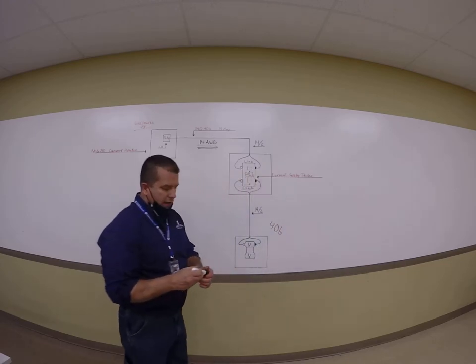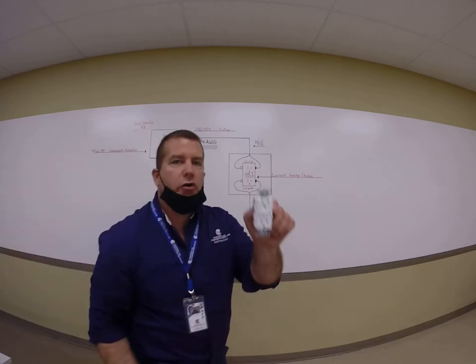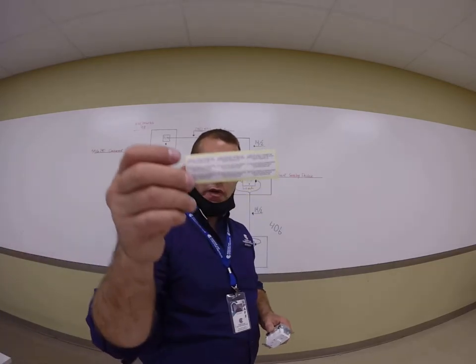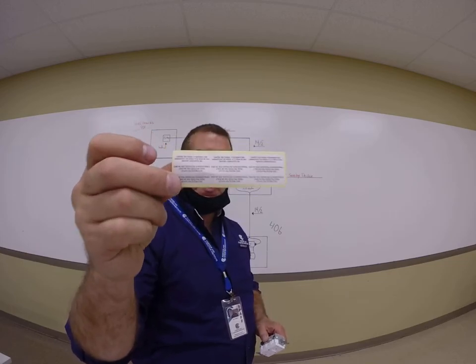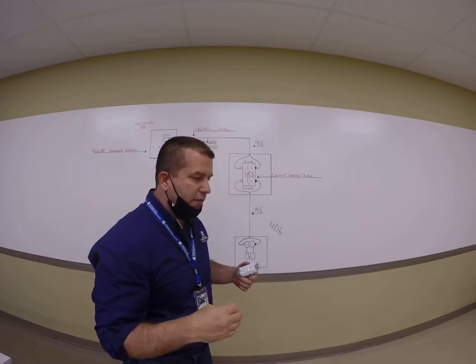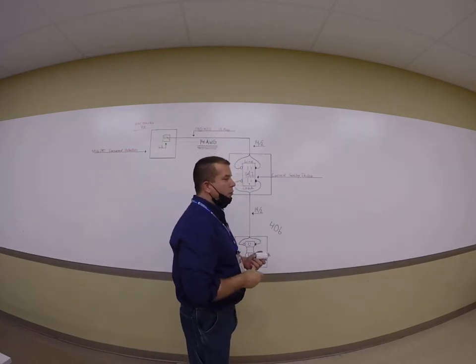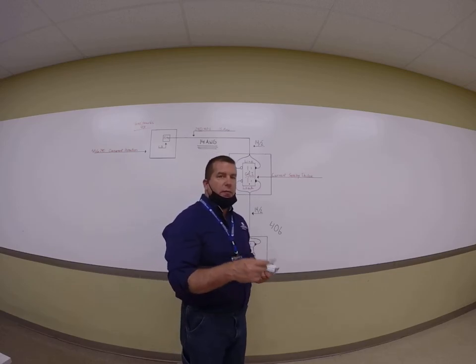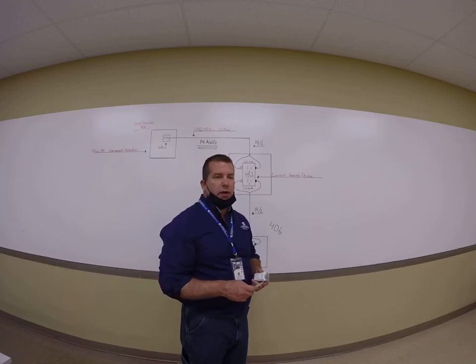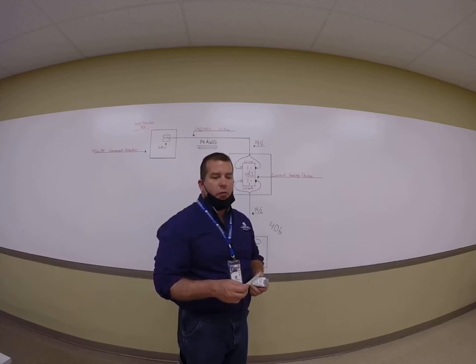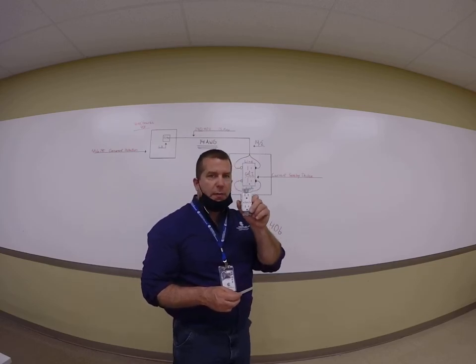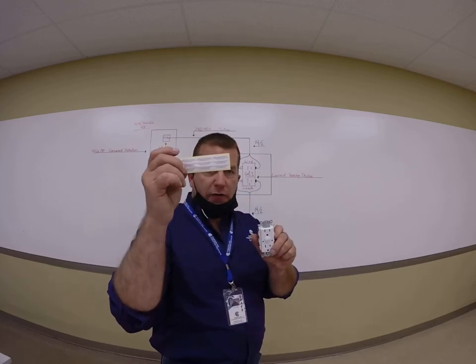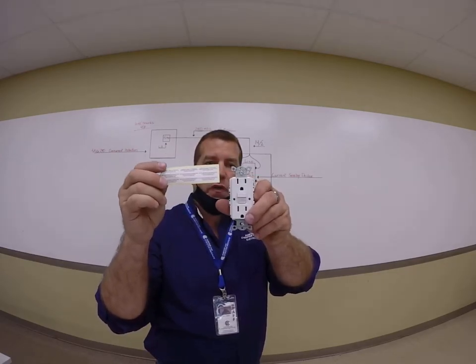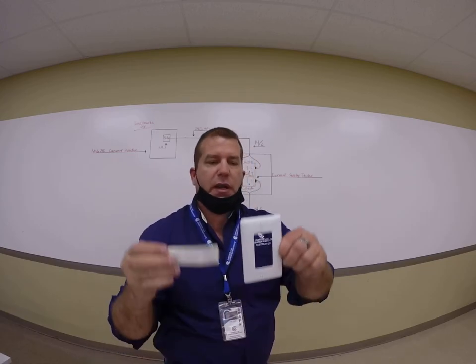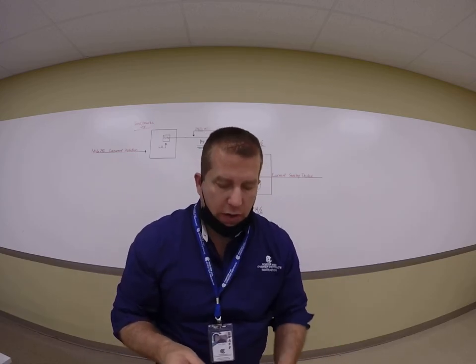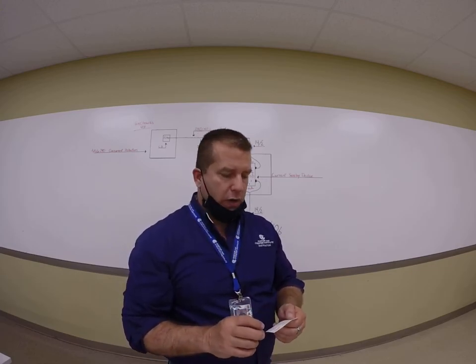So in addition to what's in the box, when you buy a new ground fault circuit interrupter, there's a pile of stickers. And these stickers are extremely important if you're replacing receptacles in somebody's dwelling. You have to realize if there's an equipment grounding conductor or if there isn't an equipment grounding conductor in the box. And the code covers that. When you meet the requirement of receptacle replacement, you're obligated by the manufacturer and the code to put the appropriate sticker on the faceplate. These stickers say anything from GFCI protected to no equipment ground.